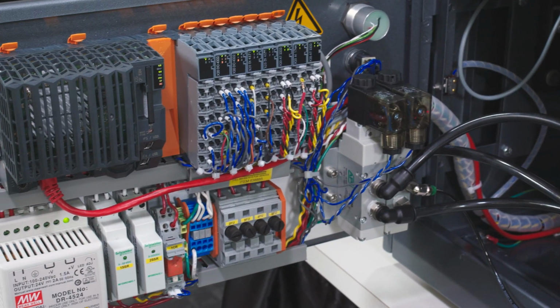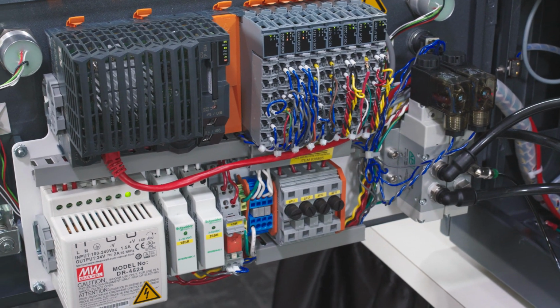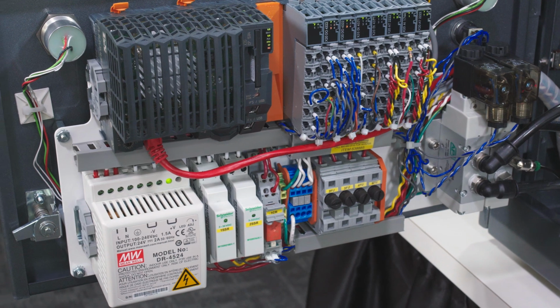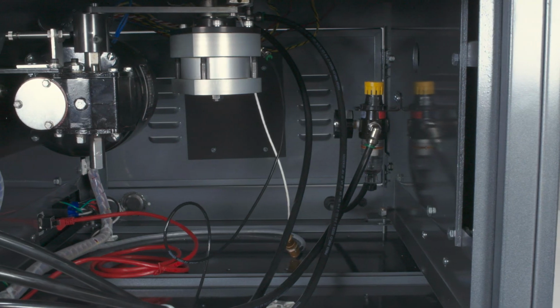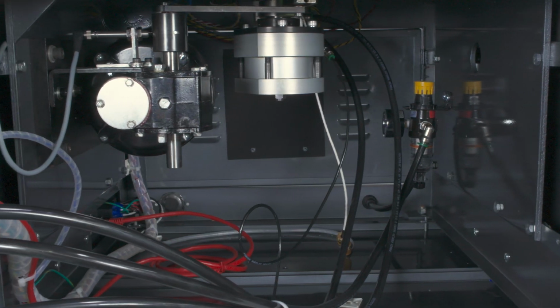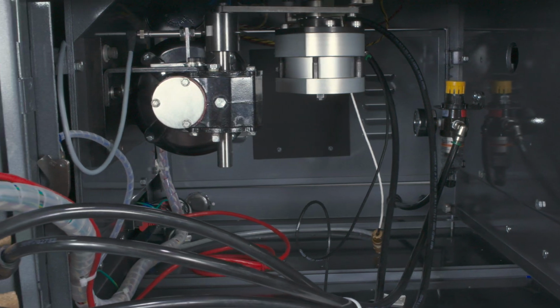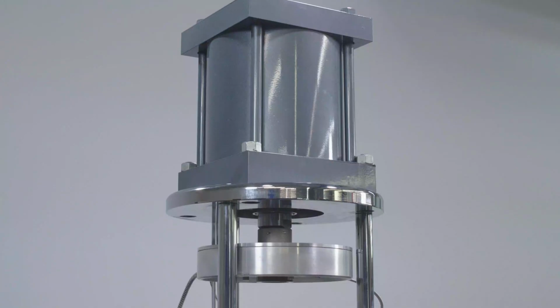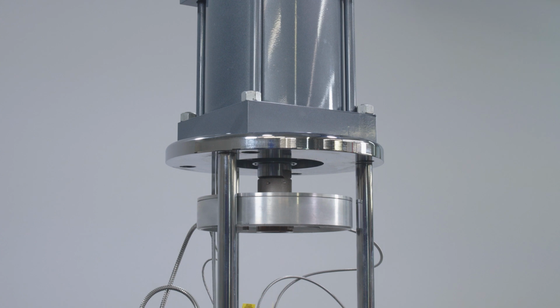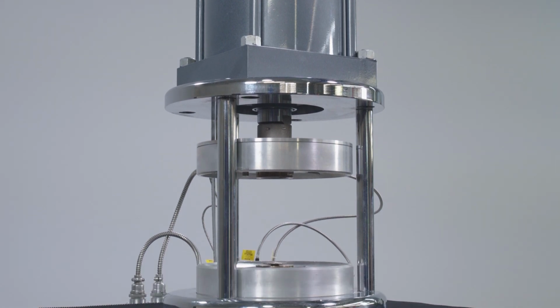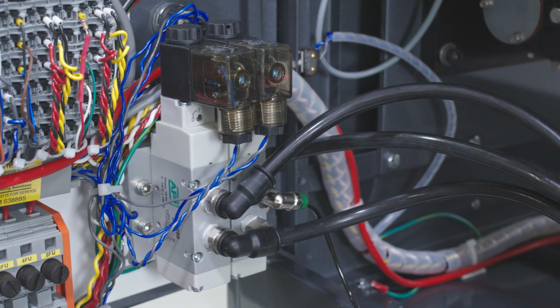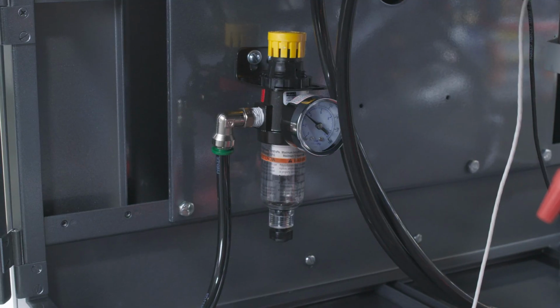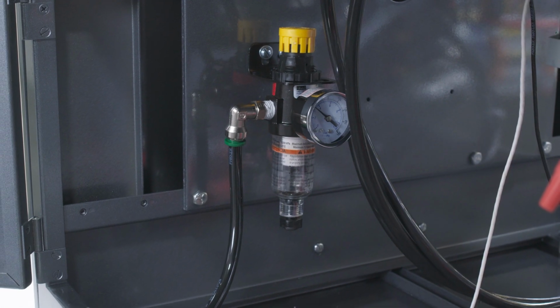Obsolete circuit boards and ribbon cables are replaced with a new PLC to unlock new potential for testing and data analysis. We rebuild the motor and gearbox and install a new timing sensor, timing circuit, bearings, and eccentric with timing pins. Following this, both the main compression cylinder and clamp cylinder are rebuilt, tested, and equipped with new 24-volt solenoid valves. The pressure regulator, pneumatic tubing, and fittings are replaced as well.